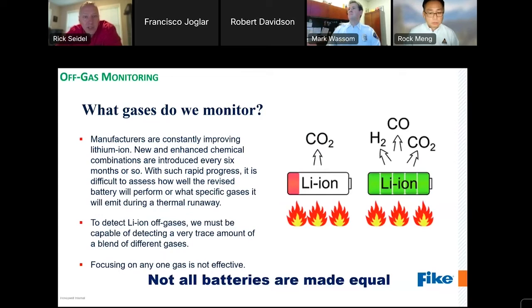With constantly changing chemistries and technologies in the designs of lithium-ion batteries, it is very difficult, if not impossible, to nail down or focus on any one given gas. To be able to detect and signal a lithium-ion off-gas event, we must be able to detect a very trace amount of a blend of different gases, typically hydrogen, carbon monoxide, and carbon dioxide, but at very small amounts that a typical standalone single-point gas detector may not recognize or measure.